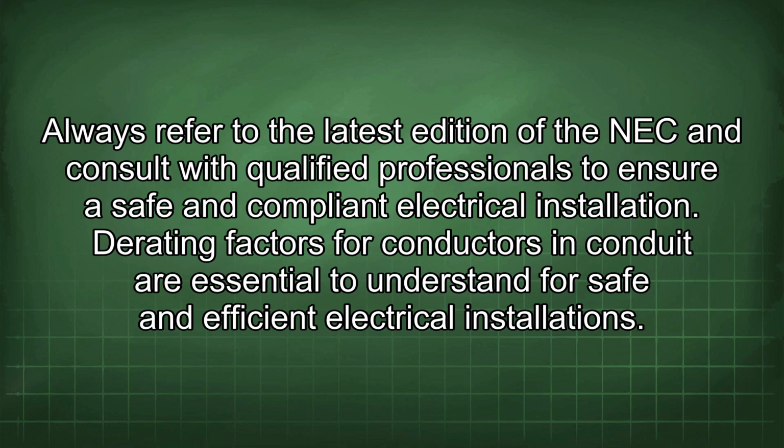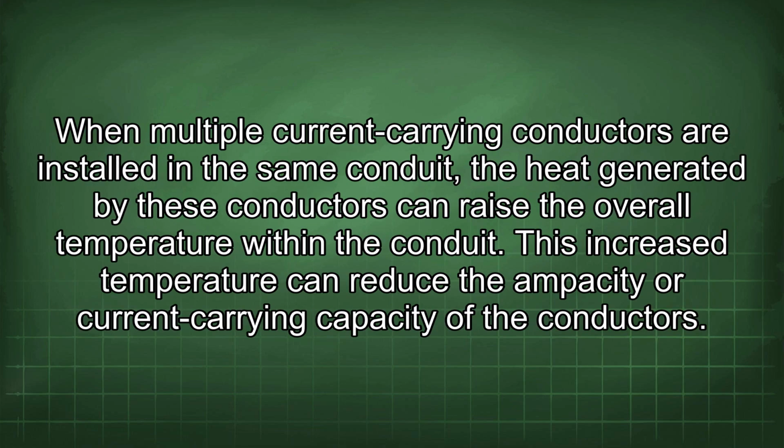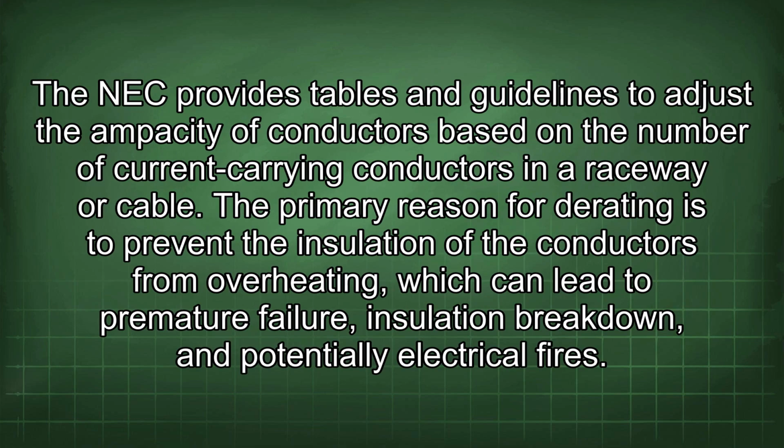electrical installation. Derating factors for conductors in conduit are essential to understand for safe and efficient electrical installations. When multiple current-carrying conductors are installed in the same conduit, the heat generated by these conductors can raise the overall temperature within the conduit. This increased temperature can reduce the ampacity or current-carrying capacity of the conductors.